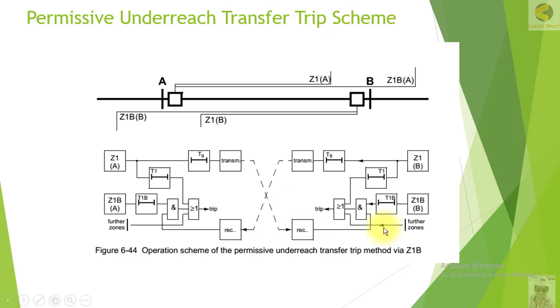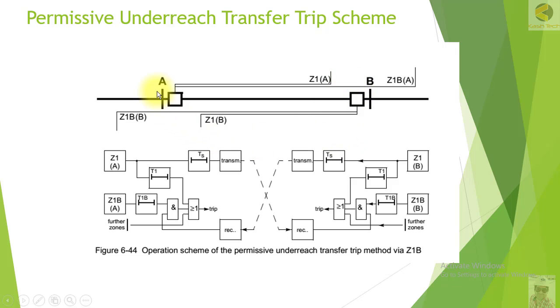Looking at the logic diagram for Station B: if the relay picks up in Zone 1, it gives a trip signal after a time delay of T1, which is normally zero milliseconds — instantaneous. Because of the OR gate, Station B trips the breaker instantaneously and sends a permissive signal with time delay Ts, also set to zero milliseconds normally, transmitting the signal to the remote end.